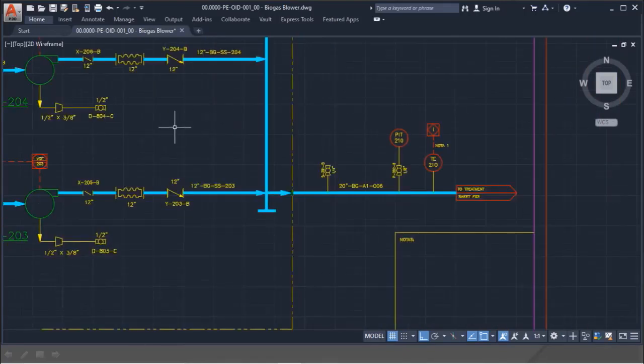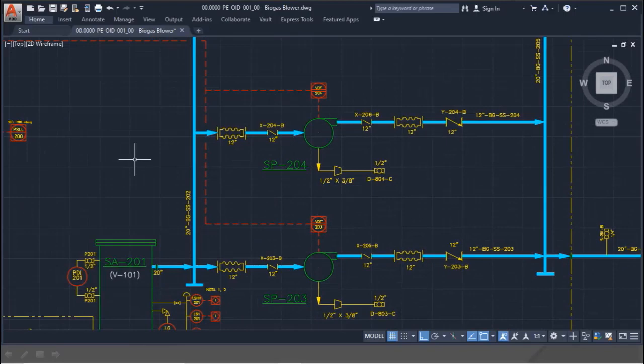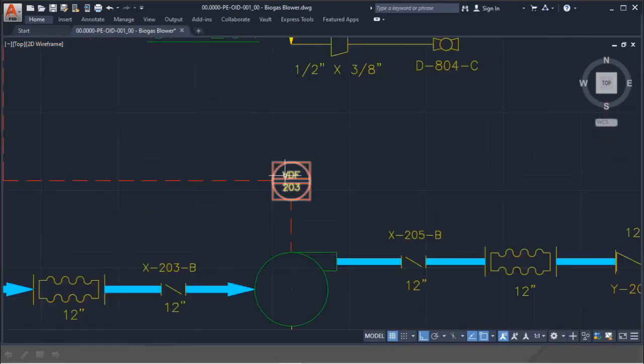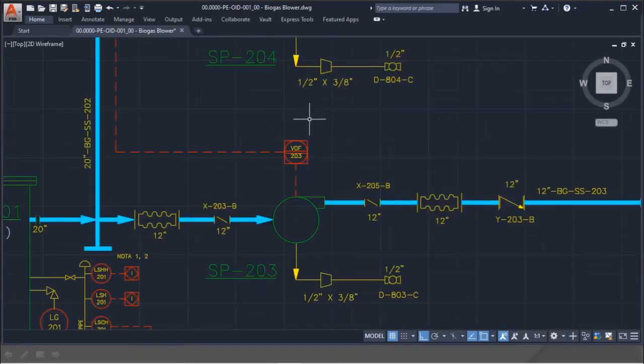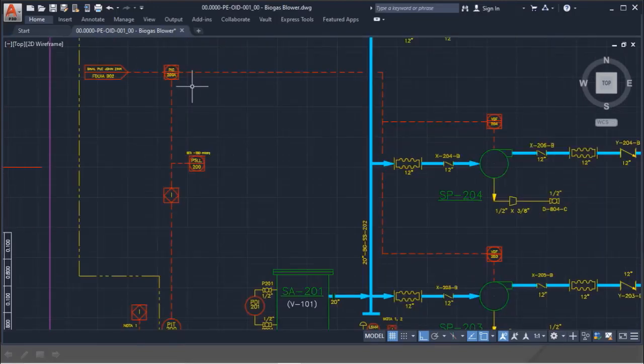Another piece of information that we can identify in this P&ID is the way that the blowers are controlled. So you can see here a VFD. It is in Portuguese, but it is a speed driver. It means that the rotation of the blower can be controlled. Based on the PIC200A set point, if the suction pressure goes below the set point, it will send a signal for the blowers to reduce their rotation. And once the blowers reduce their rotation, they will take less gas from the source. On the other hand, if the suction pressure goes above the set point, the blowers will ramp up. That means that it will increase the rotation and it will get more gas from the source.